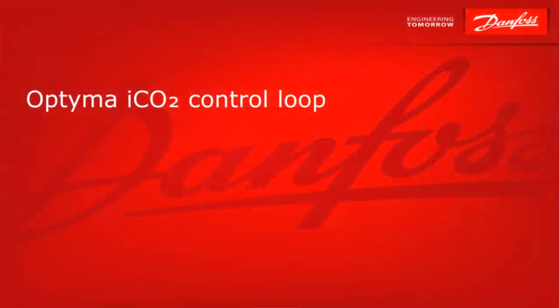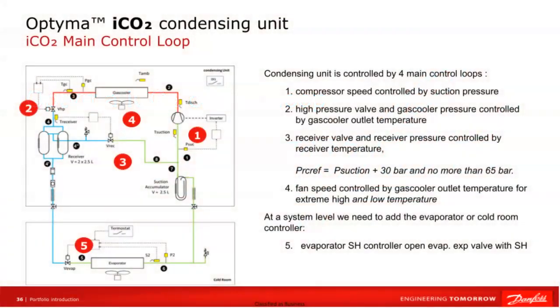Now we will move on to the part of the training where we will explore the topic of unit control, the Optyma iCO2 control loop. The unit is managed by four main independent control loops. Compressor speed regulated by suction pressure. The compressor adjusts its performance to the suction pressure level. If the pressure drops, the speed drops. If pressure increases, the speed increases. Additionally, there are fixed values of turning the compressor off and on.